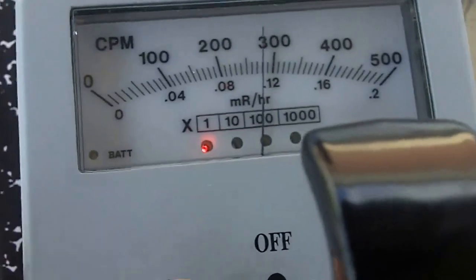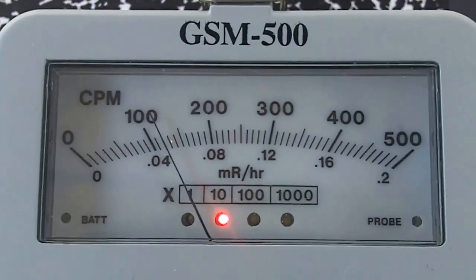Let's measure gamma rays with the back of the pancake probe. Let's go with the back only. Let's do a reset. And there we go. Gamma rays only.